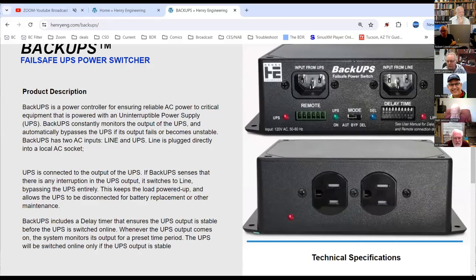If you see that the backups unit is constantly bypassing it, putting it back online, bypassing it, putting it back online, bypassing it, then you know you got a problem. But if you're not going to be able to get up to the transmitter site for a few days, you can remotely force the backups unit to permanently bypass the UPS so it doesn't sit there and switch back and forth. That'll give you time to get up there and change the batteries or do whatever you've got to do.